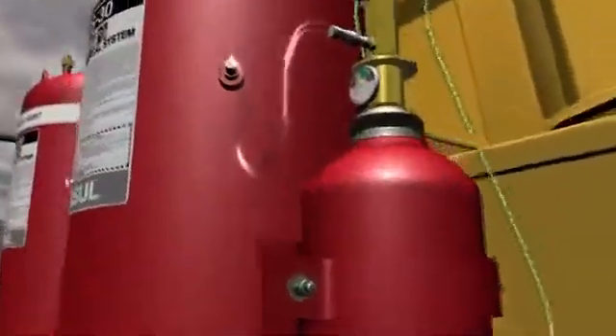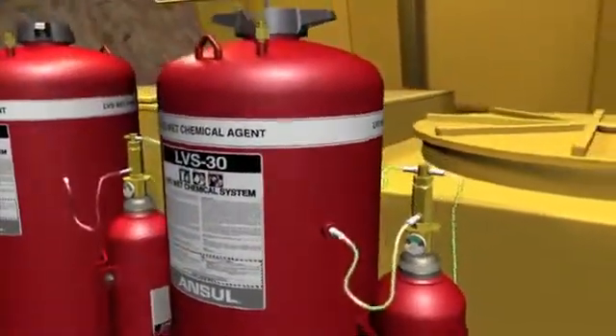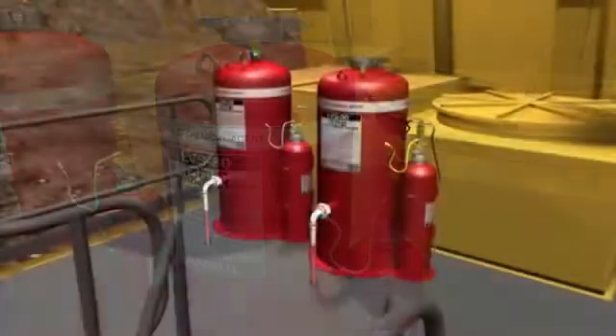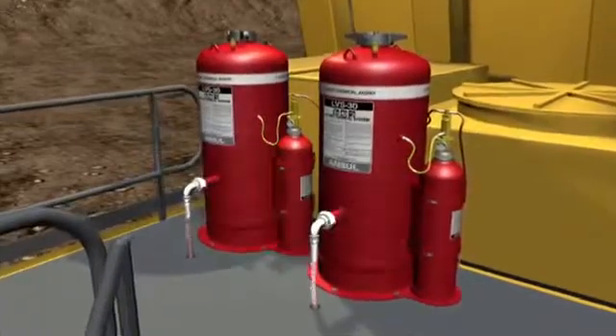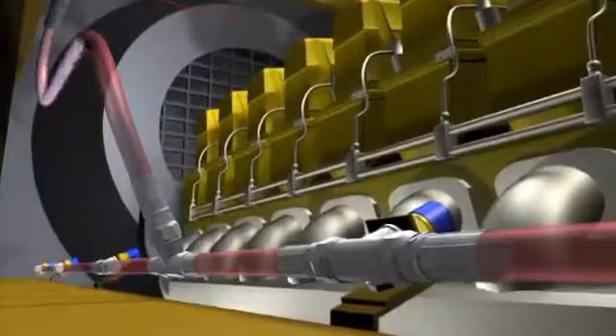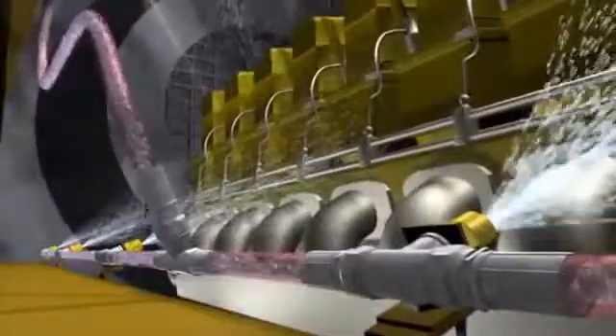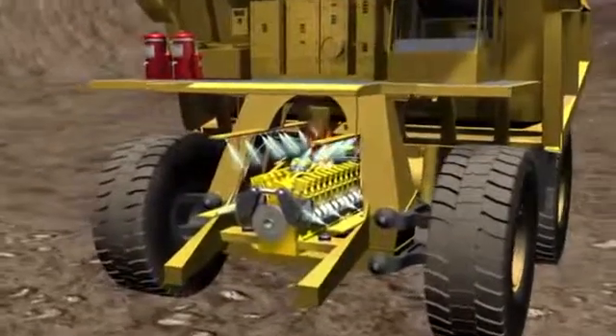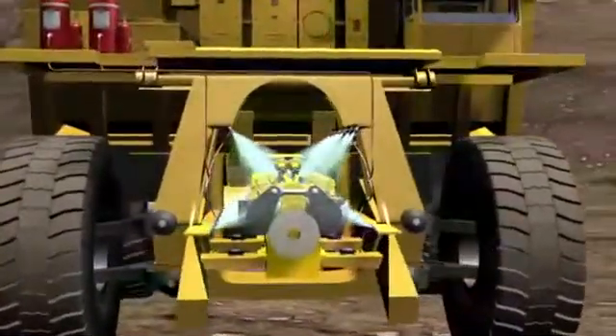The pneumatic actuator punctures the seal on the expellent gas cartridge, allowing nitrogen to flow into the liquid agent tank. When sufficient pressure is reached within the agent tank, the sealed burst disc assembly ruptures, releasing the LVS liquid agent. The LVS liquid agent is distributed throughout the hose network to nozzles designed to cover specific hazard areas. The agent is then discharged under constant pressure for the duration of the discharge to assure a full discharge pattern, quickly flooding the protected area to suppress the fire and simultaneously cool the hazard area to help prevent fire reflash.